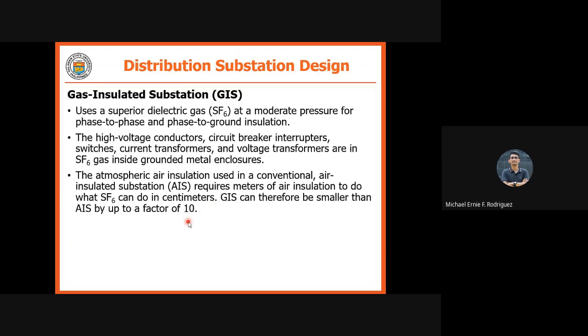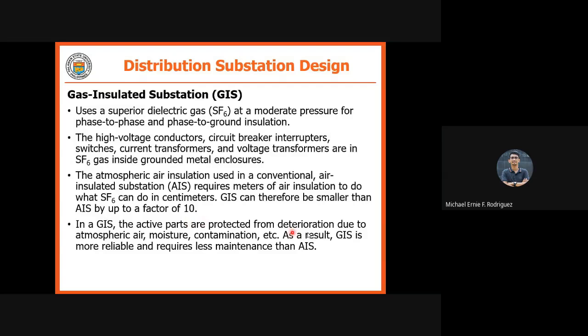So that is how small it is. Let's say we have a substation of 1,000 square meters. Okay? Let's say 1,000 square meters of substation. It can be just 100 square meters in a GIS, with the same voltage rating and the same MVA rating. The area can become just 100 square meters. That small. So from 1,000 square meters in a conventional setup of a substation with air insulation, it can become just 100 square meters. It is like just a lot, right? That small. You can have a GIS, or gas insulated substation. Okay? In a GIS, the active parts are protected from deterioration due to atmospheric air, moisture, contamination, etc. As a result, GIS is more reliable and requires less maintenance than your AIS.